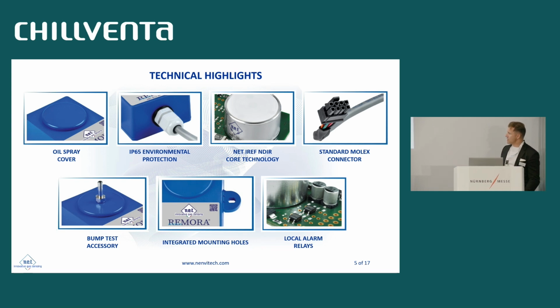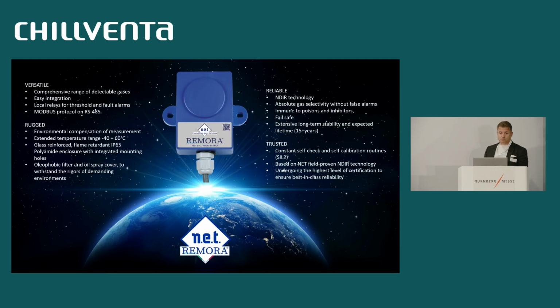Integrated mounting holes to be installed directly inside equipment with an easy solution, and it provides two local alarm relays, one normally connected to fault condition and one normally connected to the alarm threshold at overpassing, for example 15% LFL, 20% LFL, that is fully customizable. It is very versatile in the range of gas, in the easy integration it provides, with the digital communication, with the threshold outputs, with the local relays.